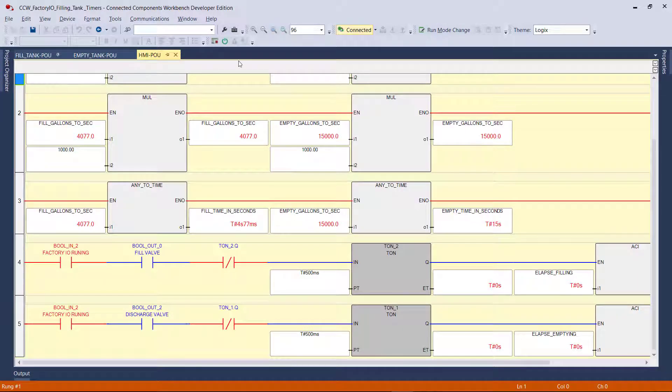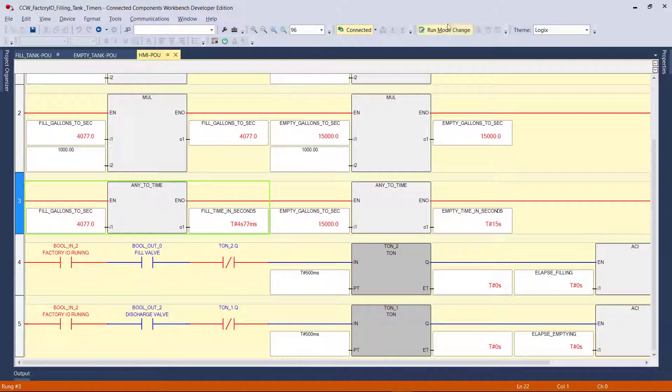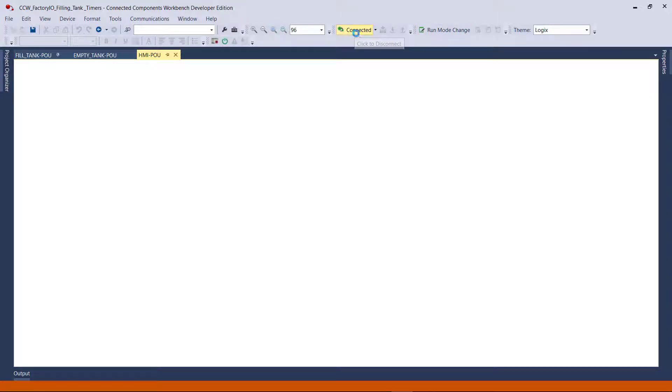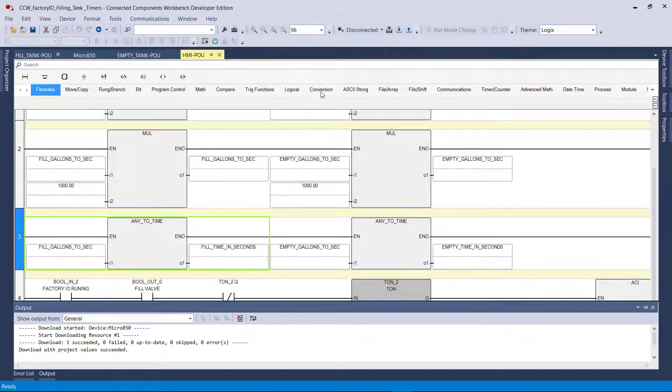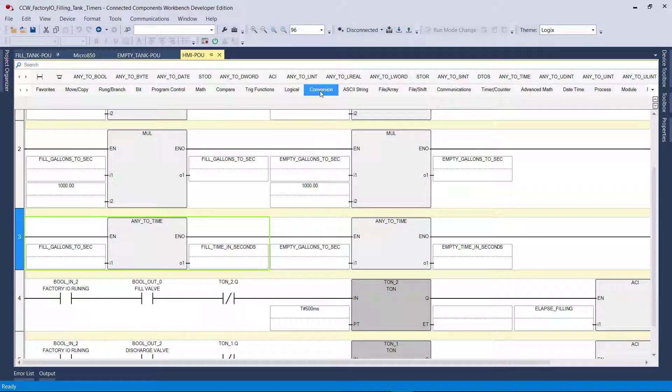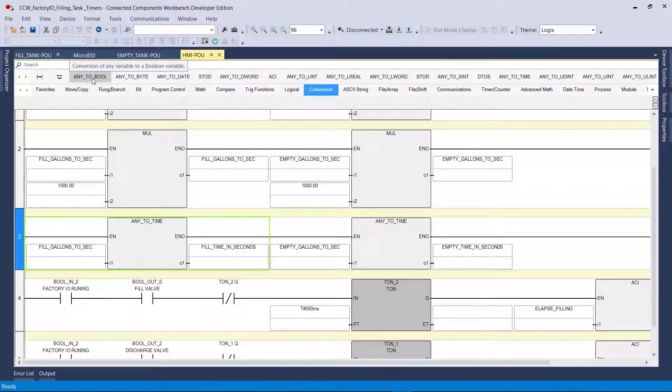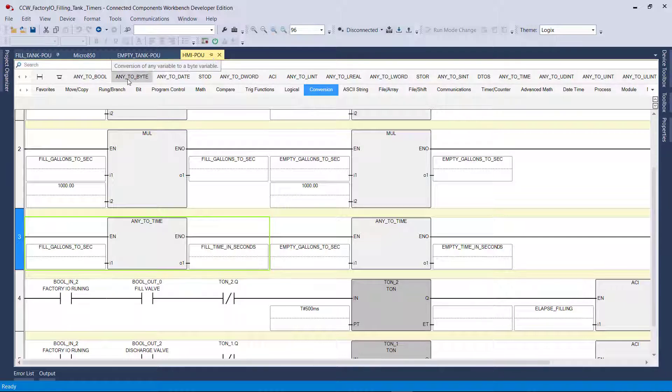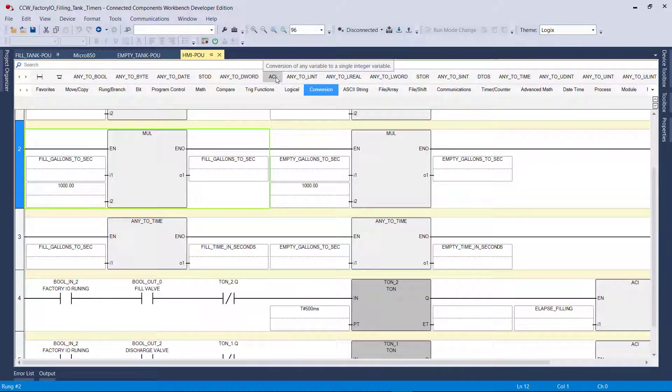Luckily, CCW has these beautiful functions called any2time. If you just disconnect over here and go to the conversion tab, you see all these functions? Any2boolean, so this converts any variable to a boolean type, or any type to a byte type. So I used one of those, I used this one over here. It's called conversion of any variable to a single integer variable.